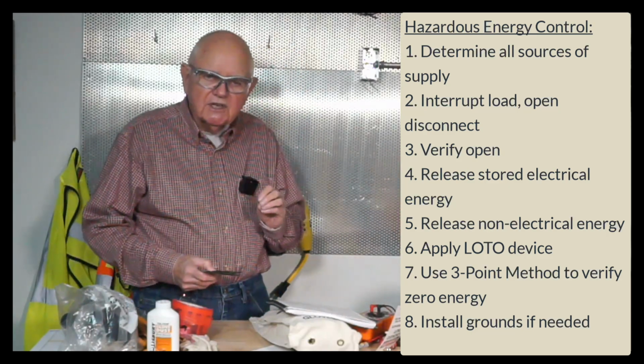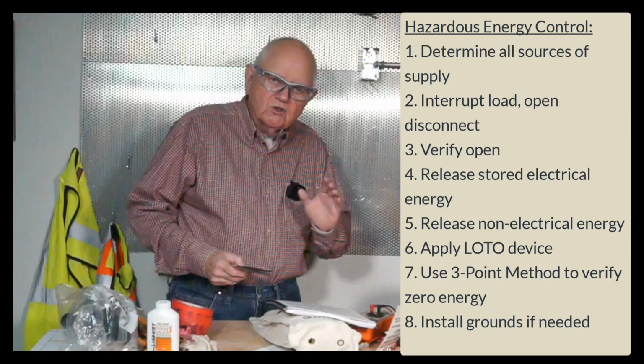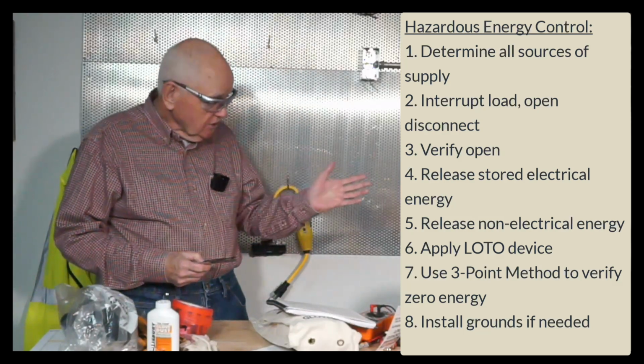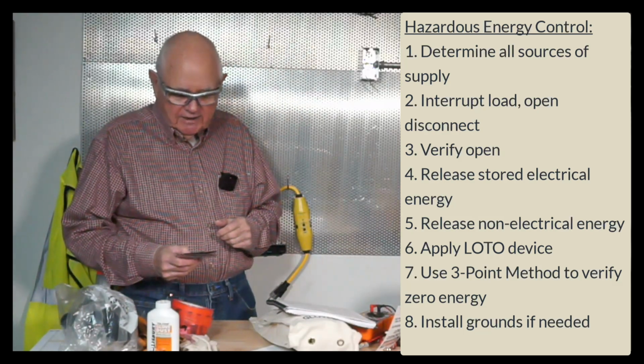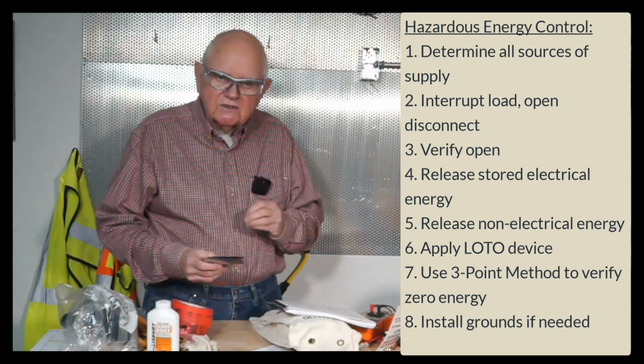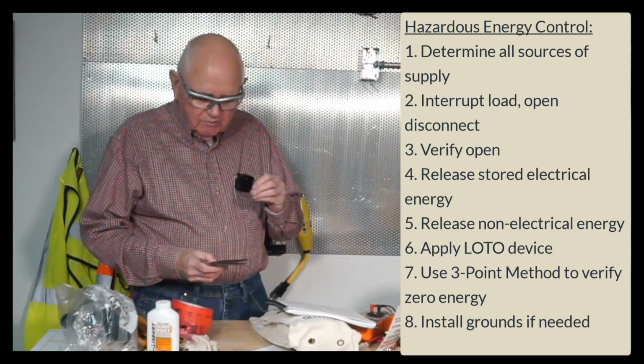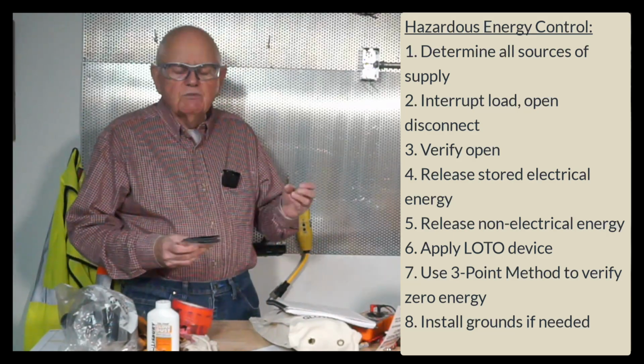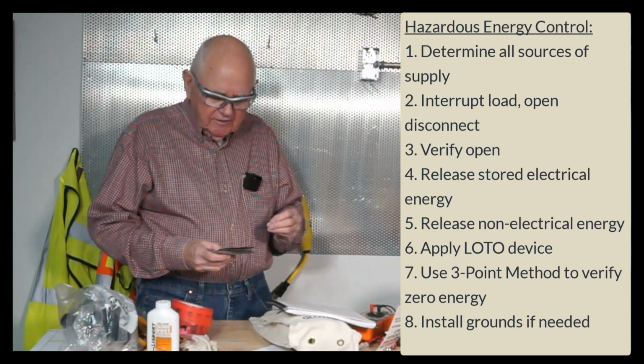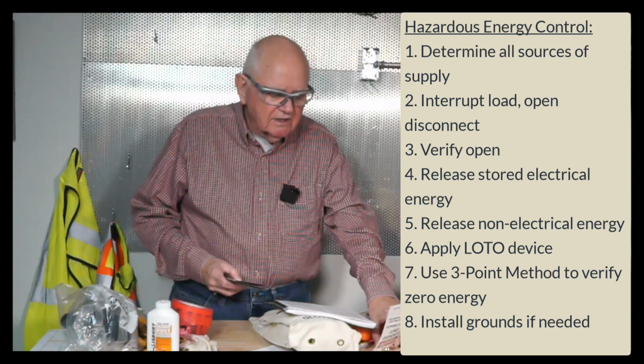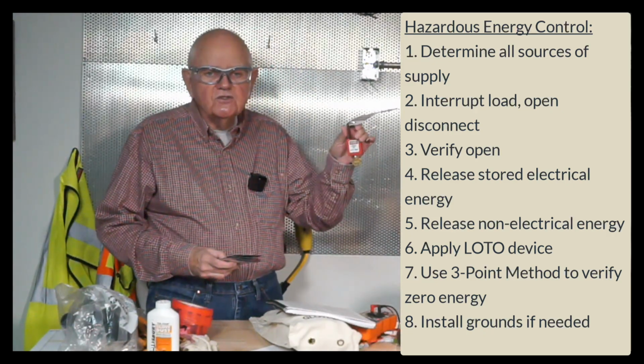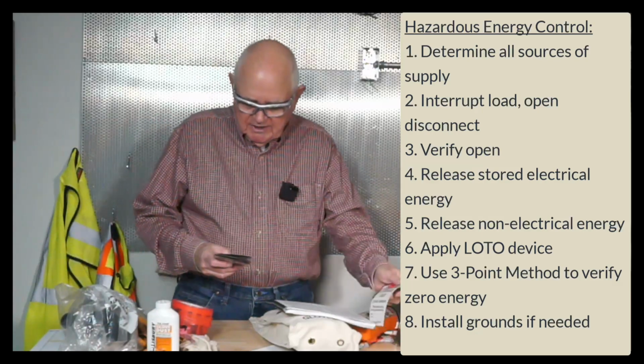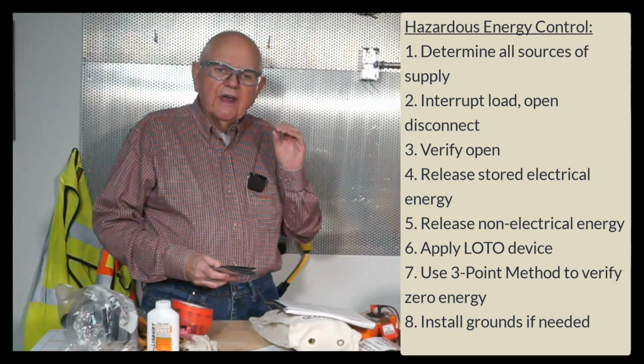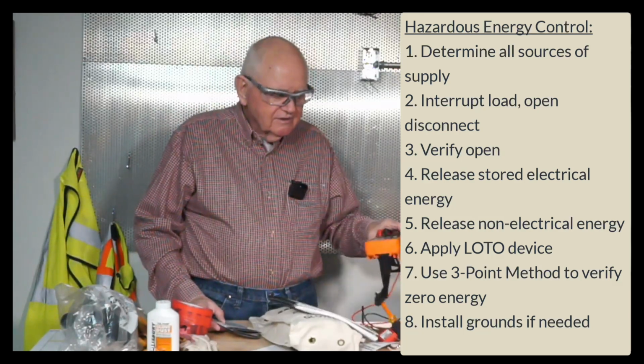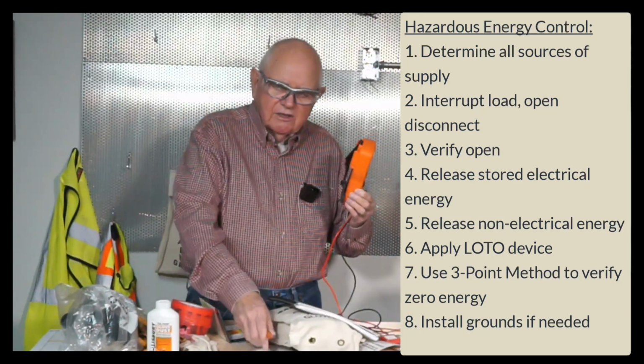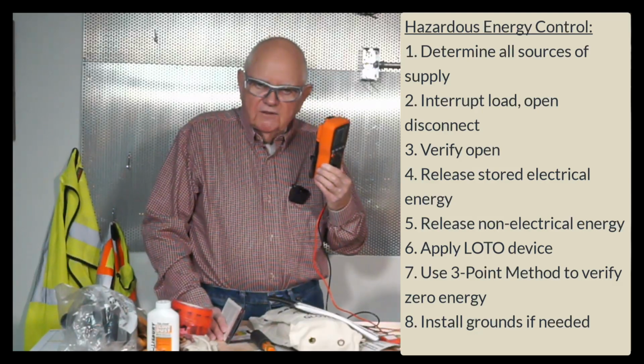The next step says, wherever possible, visually verify that. So if I can look at the knife blades, if I have the circuit breaker I've racked out, I can visually verify all of that. Release any stored electrical energy is the next item, and then release or block any stored mechanical energy as well, spring pressure and so on. And then apply your lockout tagout device. So whatever your procedure is for hazardous energy control, make sure you're following that, but apply your lockout tagout device. Then use an adequately rated portable test instrument. So your meter, and go through and verify the circuit de-energized.